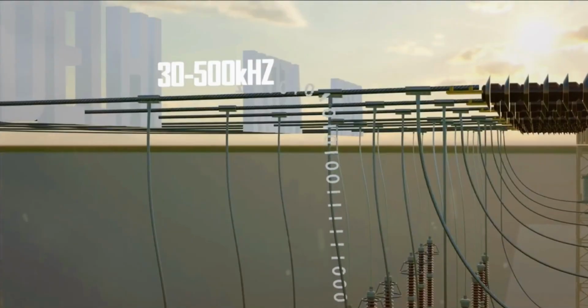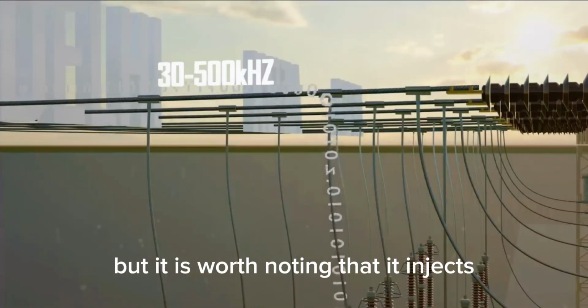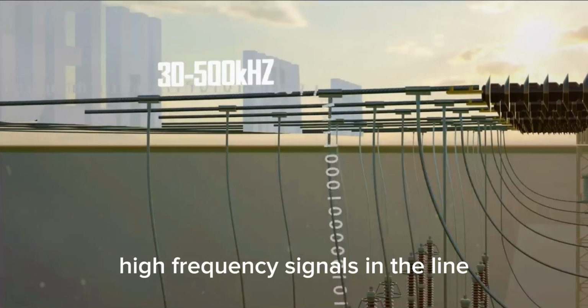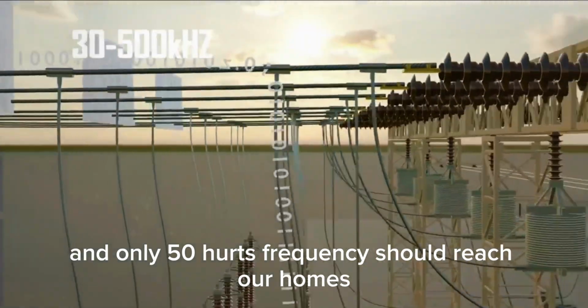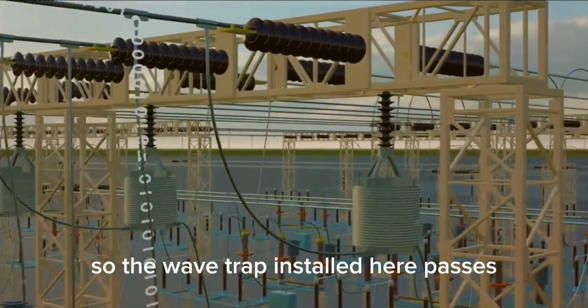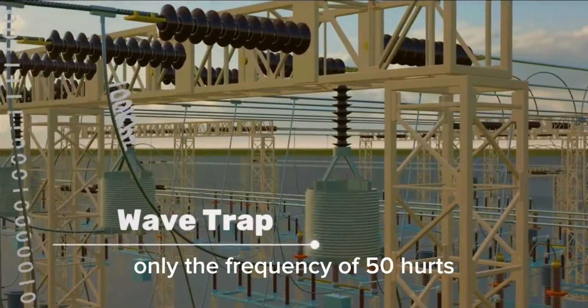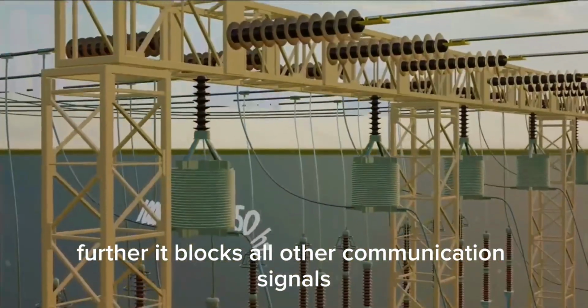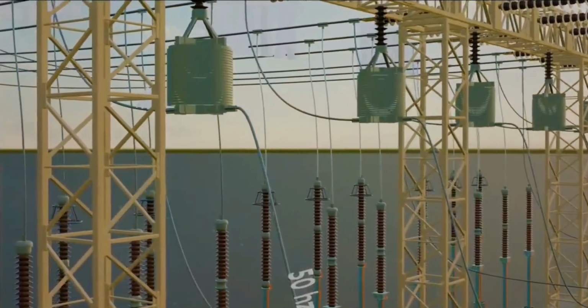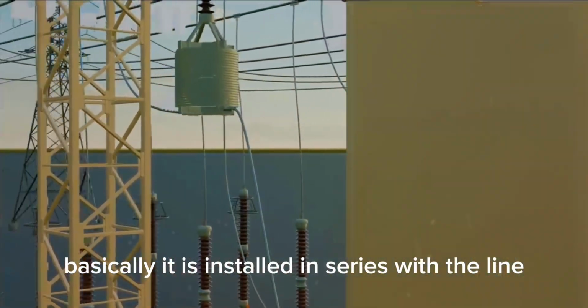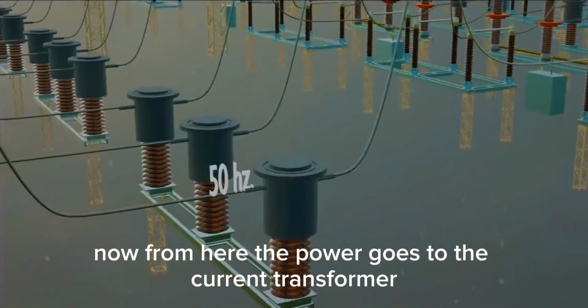transmission line. But it is worth noting that it injects high-frequency signals in the line, and only 50 Hz frequency should reach our homes. So the wave trap installed here passes only the frequency of 50 Hz further. It blocks all other communication signals. Basically, it is installed in series with the line. Now from here the power goes to the current transformer.